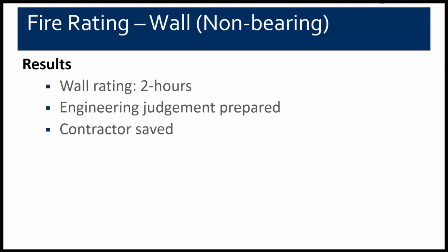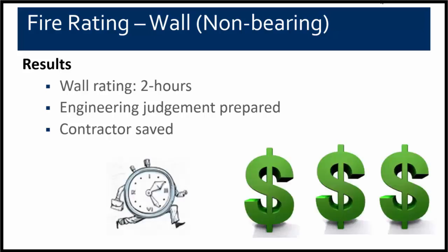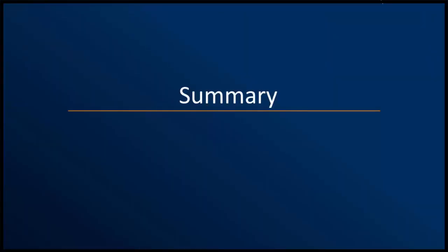The result was an engineering judgment and documented letter with the associated calculations showing that the existing wall assembly provides a minimum of a two-hour fire rating when exposed to a fire on either side. WJE got to show a client how multiple offices and service offerings, including the JTC, could work together to solve a building issue involving fire resistance ratings. The client and contractor were able to save time and money because additional work to bring the existing wall to the code-required two-hour fire resistance rating was not necessary. It should be noted that the windows in the wall were planned to be replaced with two-hour fire rated construction.